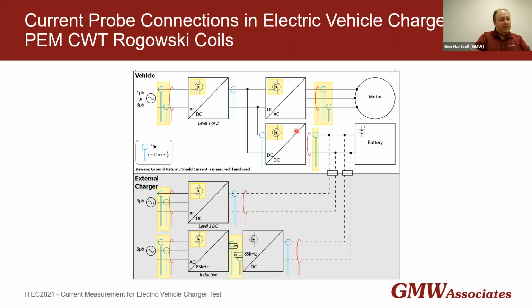Another place that I've highlighted, which you may not expect actually, is the battery, the DC battery mains. And here we're taking advantage of the fact that it's insensitive to DC. Here we're looking for a ripple current, either intentional or unintentional, on top of the DC current. And the DC will be completely ignored. The Rogowski coil will only measure the AC current.